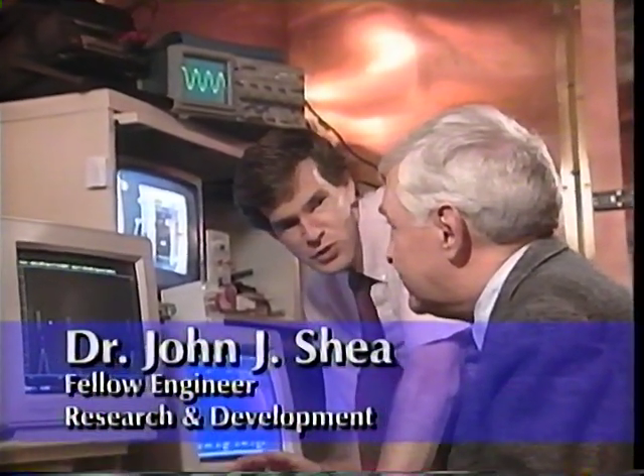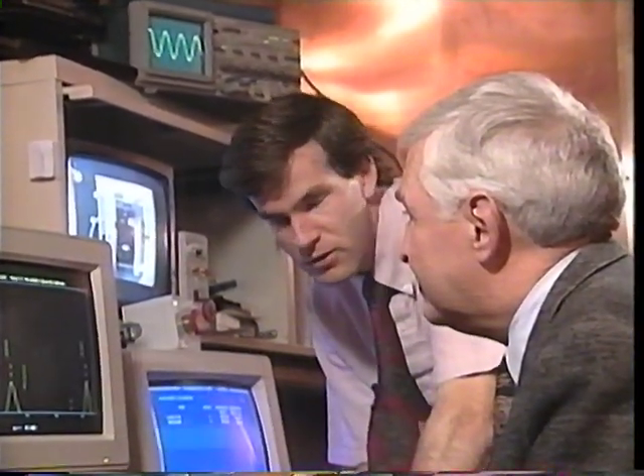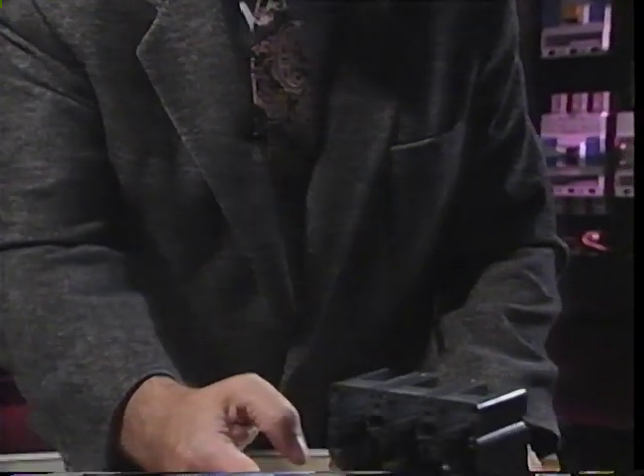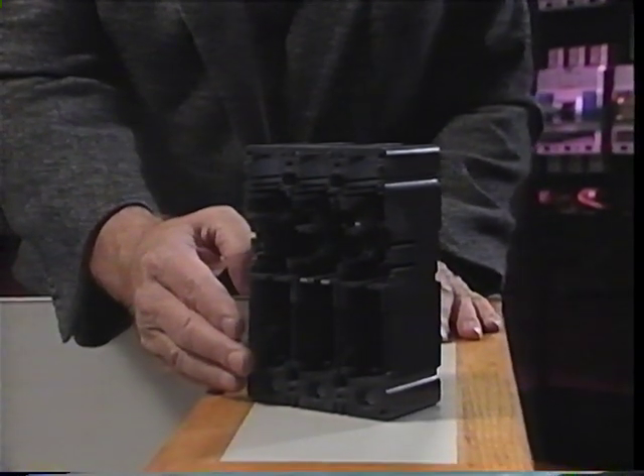The process is as important as the physics. The strength of a breaker depends heavily on the way its case is molded. There are secrets in the fast-moving art of the molding process, reasons why these breakers have the strength to tame a lightning bolt and then go back to work. Even that is just the beginning of the challenge, because those same materials have to do a job at a level of molecular physics. The breaker's materials are one of the sources of ionized gas that are generated inside. Under a fault current, molecules are torn from the internal surface of the breaker's materials and given an electrical charge, forming much of the plasma that conducts the arc. So the materials, which look like a simple box, are part of the physics of the interruption process itself. A box that must be designed to create a particular kind of gas that's different.